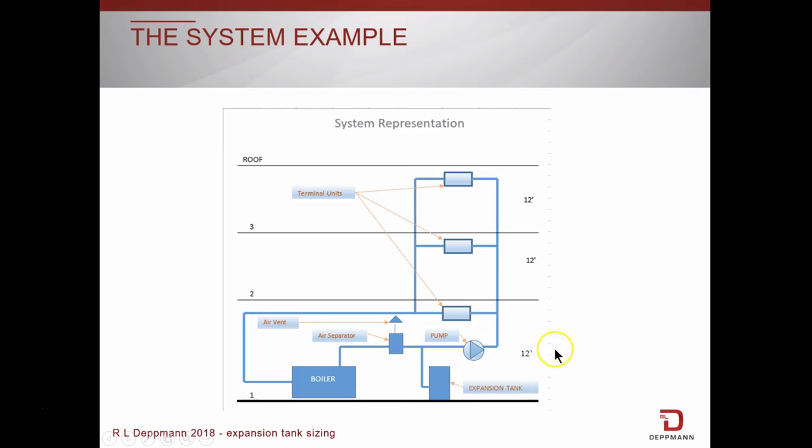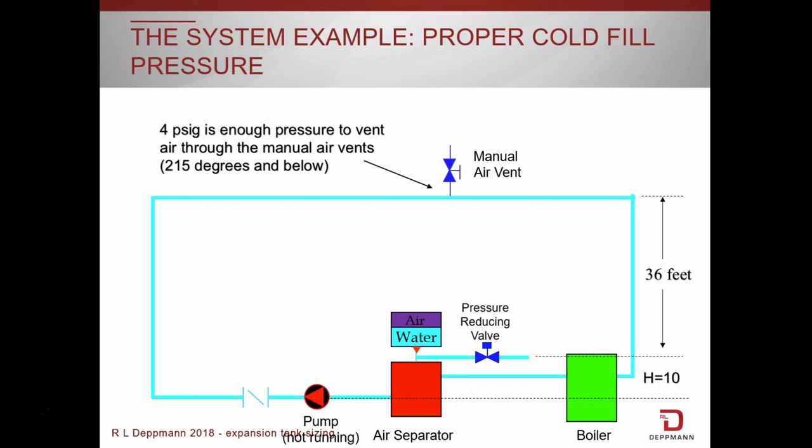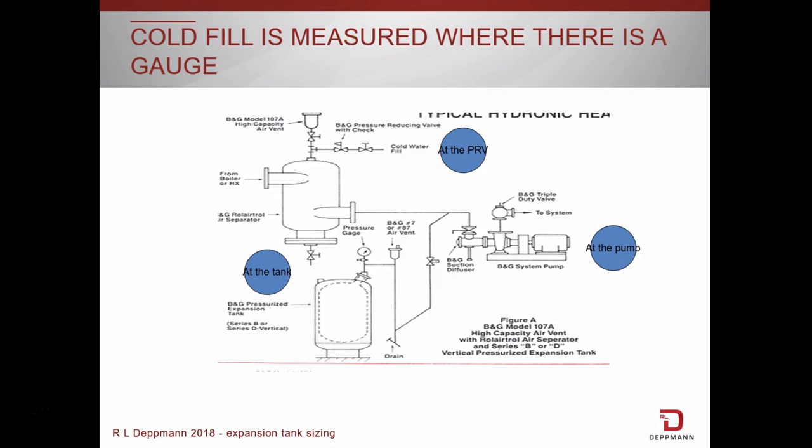So back to our building example. Note the elevations shown here on the side. Here you see where the PRV ties into the piping system. In this example there is 36 feet of elevation from the PRV to the top of the building piping system. 36 feet head equals 15.6 psig. Now we add 4 psig for the air vents and the cold fill pressure at the PRV is set to about 20 psig.